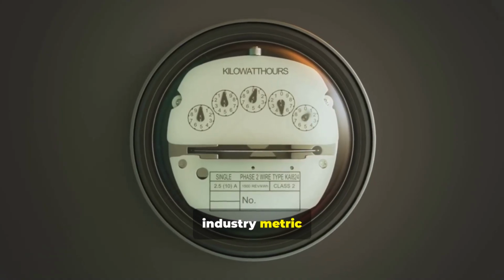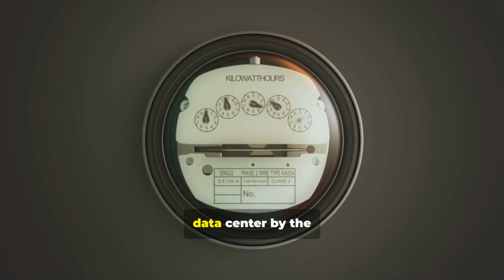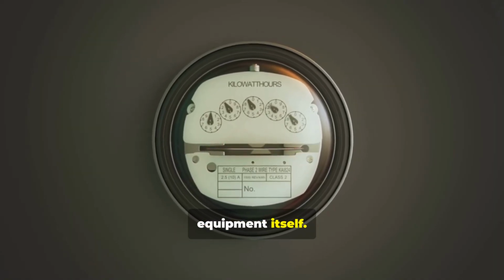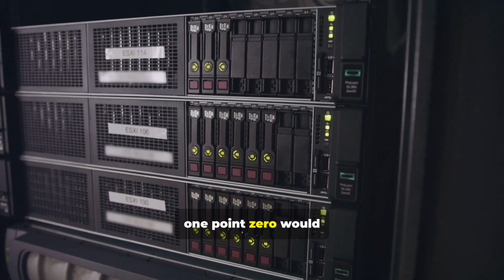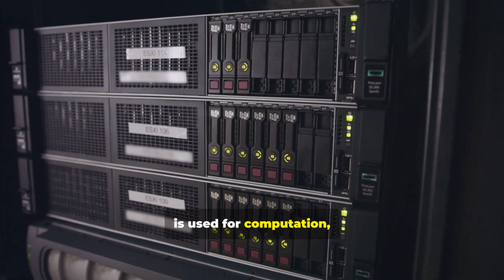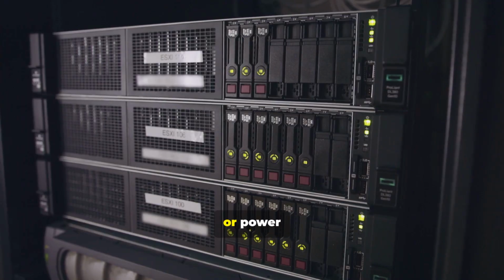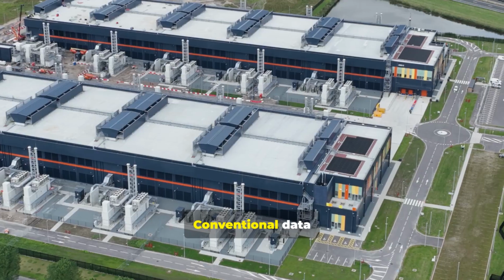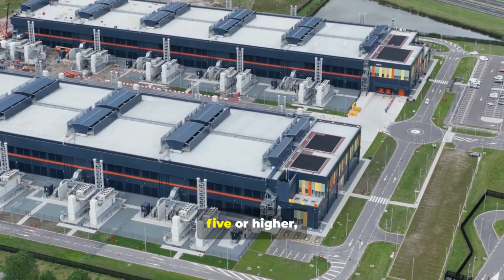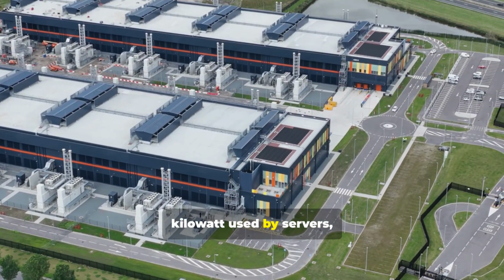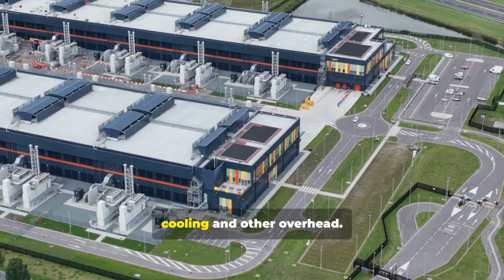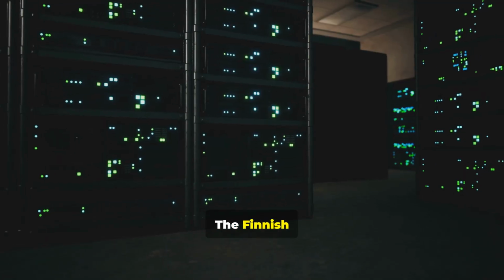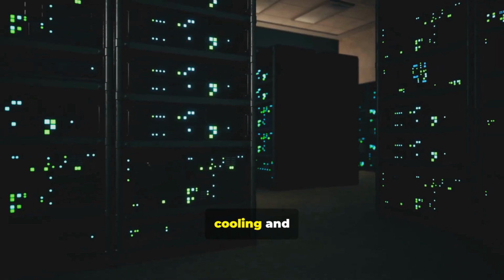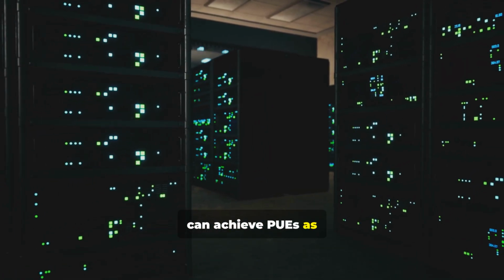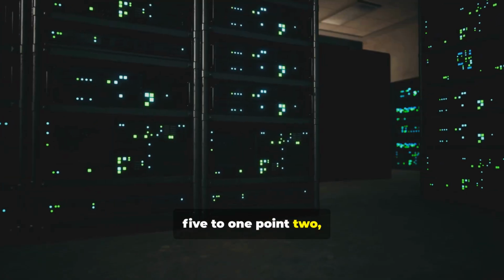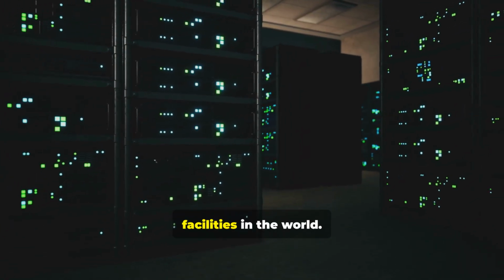PUE is a standard industry metric calculated by dividing the total power entering a data center by the power used by the IT equipment itself. A perfect PUE of 1.0 would mean that all energy is used for computation, with none spent on cooling, lighting, or power distribution losses. Conventional data centers often have PUEs of 1.5 or higher, meaning for every kilowatt used by servers, an additional half kilowatt is used for cooling and other overhead. The Finnish underground data centers, by leveraging free cooling and efficient heat recovery, can achieve PUEs as low as 1.15 to 1.2, placing them among the most energy-efficient facilities in the world.